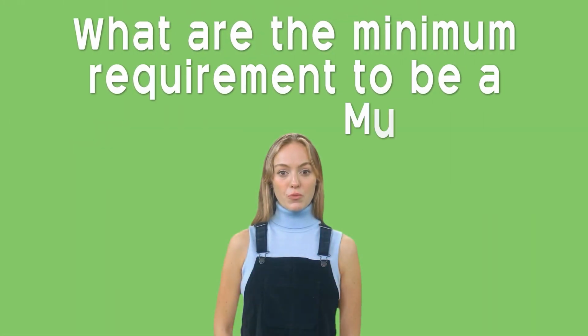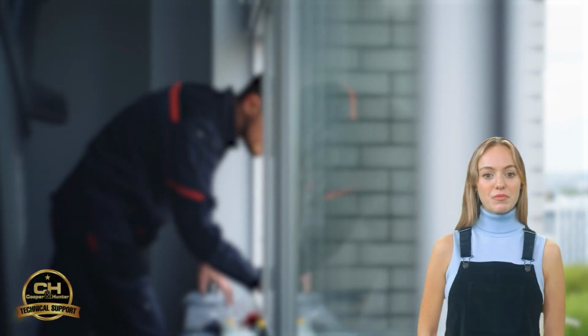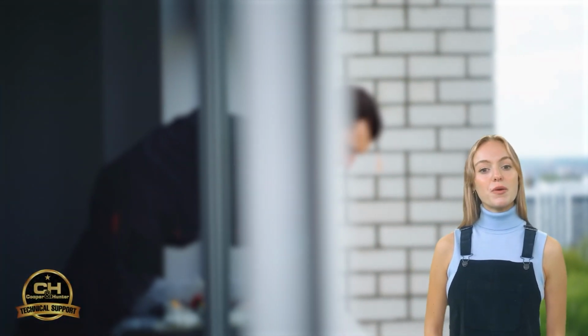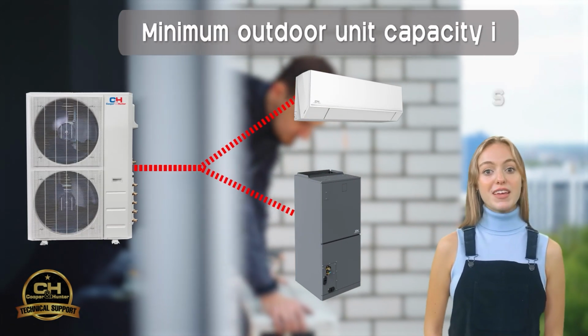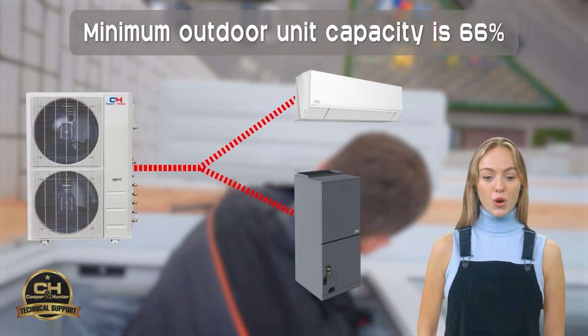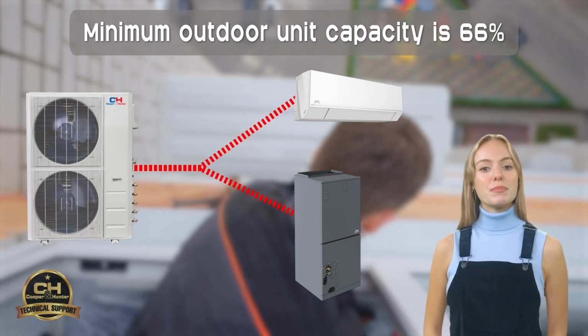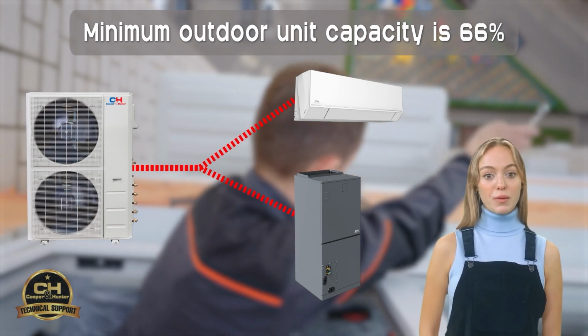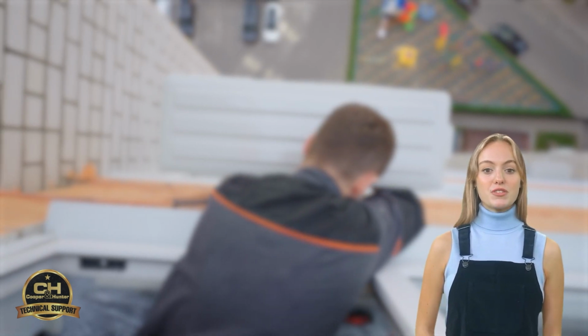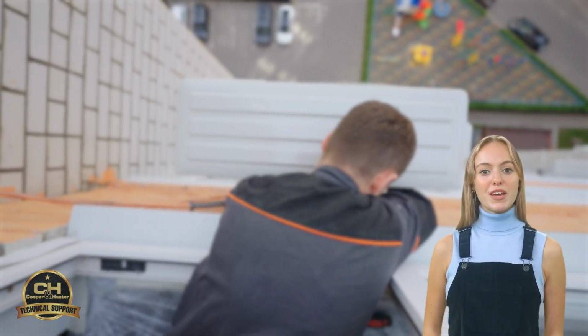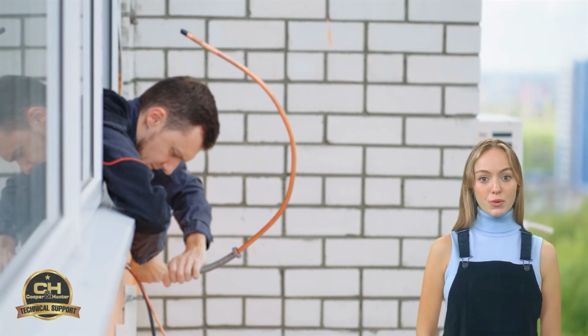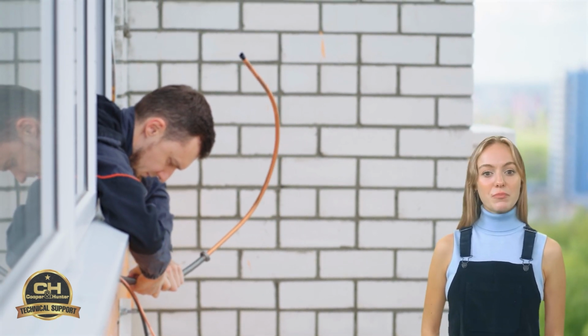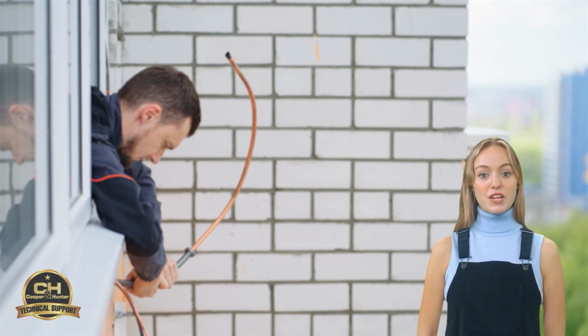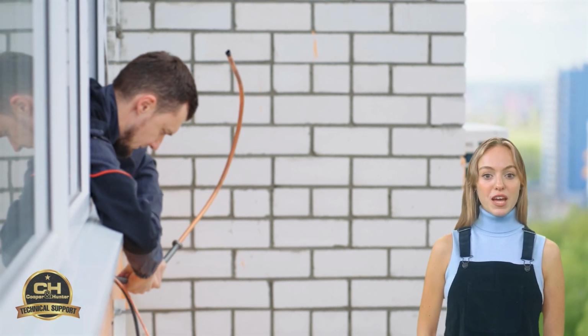What is the minimum requirement to be a multi-zone system? For the multi-zone systems, there is a minimum requirement of 2 indoor units connected to the same outdoor unit, and the total capacity of the indoor units must be at least 66% of the total capacity of the outdoor unit. This is to ensure that the system can operate properly and maintain a balanced refrigerant flow and pressure. If the minimum requirement is not met, this will affect efficiency and may fail to provide adequate cooling or heating. Failure to do so will also damage the unit and void the warranty.